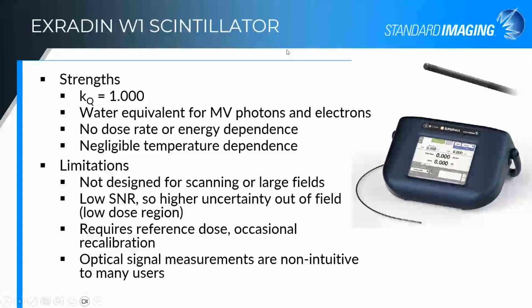With the W1, the strengths of this detector are that it has that beam quality correction factor of unity. So you don't have to be concerned with the change in energy spectrum as you're going to these small fields or as you're going to deeper depths. That's really the confirmation that it is water equivalent for MV photons and electrons. We have not seen dose rate or energy dependence with this for standard megavoltage therapy beams. There is a negligible temperature dependence. It's about 0.1% per degree Celsius. I can look that up if you have a concern. Generally speaking, if you're doing all of your measurements at room temperature, you don't have to worry about accounting for temperature.